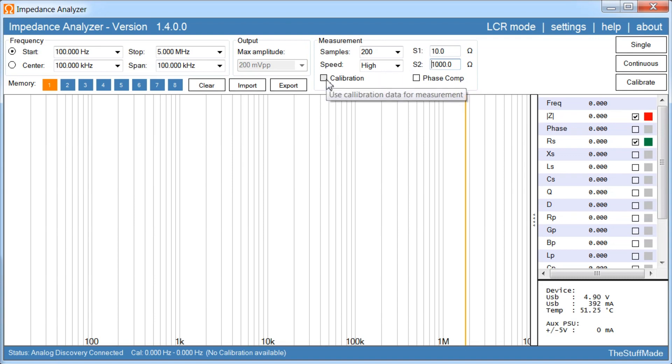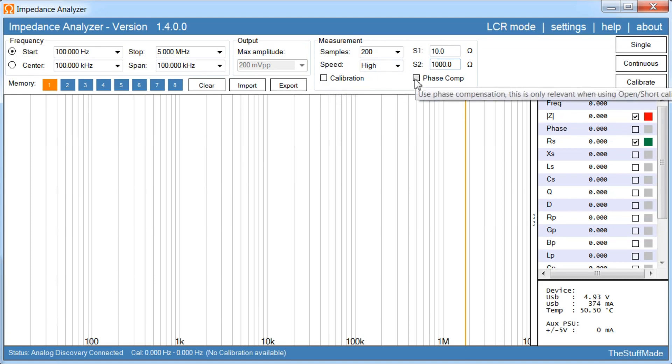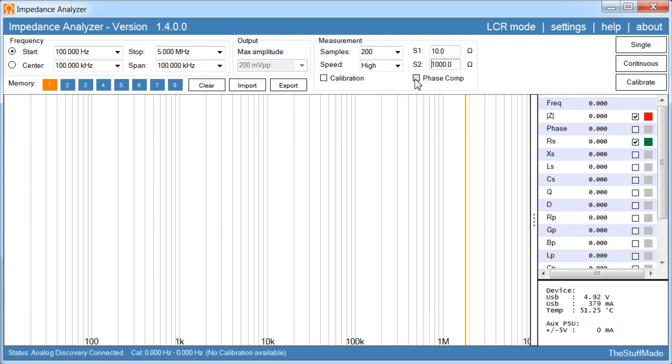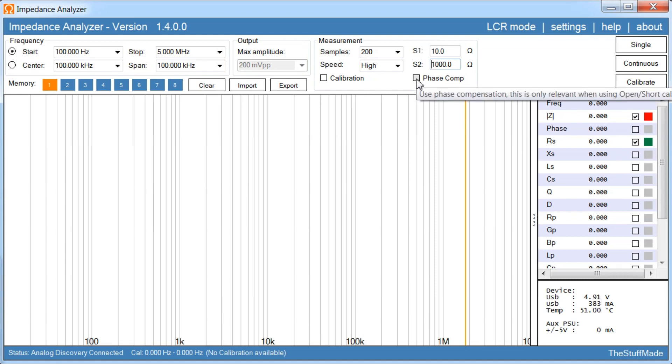Then we have calibration, whether you want to use calibration during the measurement or not. And then we have a little bit experimental here, phase compensation. This is because when you are running higher frequencies there is going to be a little bit of phase shift, so it will try to compensate for that. But as you can see the description here, it is only relevant for the open short calibration.